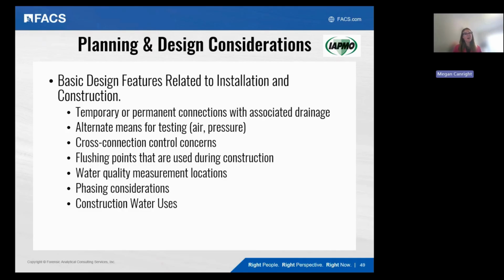The water management team can also make recommendations for where cross-connection control has to occur, and for pressure testing the system. Most times water is used for pressure testing, but there are alternatives like nitrogen or dry air, which can help minimize the period of time that water sits stagnant in the pipes. If you use air, you don't have to fill and test the system until the commissioning phase later on.